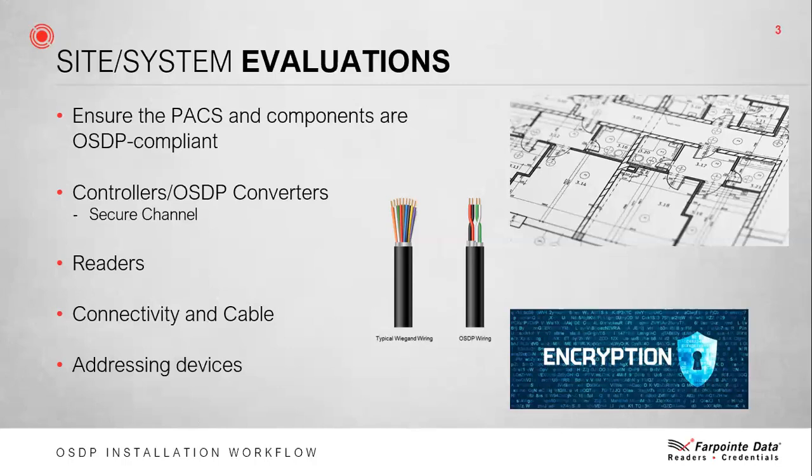Using multi-drop via the RS-485 layer can provide some advantages: fewer conductors, which saves on total cost; longer wire runs — for example, RS-485 can go up to 4,000 feet on the proper cable; and less need for controller real estate. If you decide to utilize RS-485 in a multi-drop topology, the readers you use must facilitate the ability to be assigned an address from an OSDP controller.